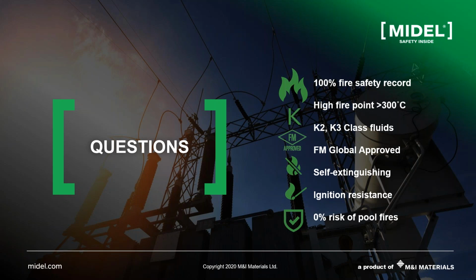Yes. The next question is also quite a nice question. If sitting with a 2.5 MVA transformer at 11,000 volts step down, and they've retrofitted the transformers with natural ester, but they don't really have a good indication of what typical oil temperature settings and winding temperature settings would be. Do you know that off by heart, or is it specific to each transformer? No one will know because it is specific, but the range is very limited here. My own engineering guess, for an 11 kV, 2.5 MVA transformer, is that the top liquid temperature will increase by only a few degrees, maybe 2 or 3 degrees. So I would maybe add 5 degrees to that limit, and that should be okay.